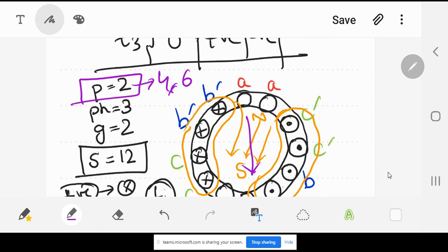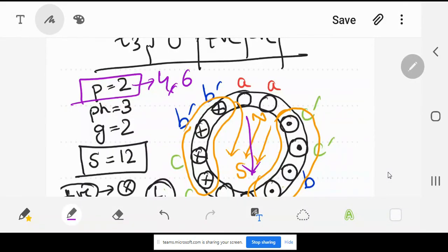So this is a very important thing. Whenever in the industry you want to change the direction of the machine, whether it is a three-phase 3-wire or a three-phase 4-wire, you have to swap any two of the phases, not the neutral one. The neutral should not be swapped, otherwise it will create balancing problems. So only two phase wires should be swapped, and if you do that, you are changing the direction of your machine.